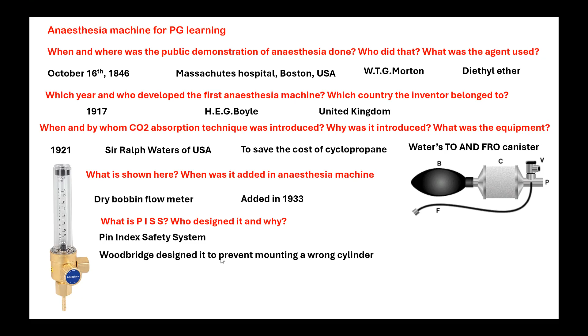What is PISS, and who designed it and why? What is the expansion for it? Woodbridge is the person, very good. But what is the expansion for this acronym? Pin index safety system. Excellent. And why was it designed or added to the machine? Sir, to avoid wrong cylinders being connected. Excellent, to prevent the mounting of a wrong cylinder in the yoke. The place where you mount the cylinder on the machine is called the yoke assembly, or yoke hanger, whichever way you want to call it. So the expansion is pin index safety system, and Woodbridge designed it to prevent mounting a wrong cylinder on the yoke.